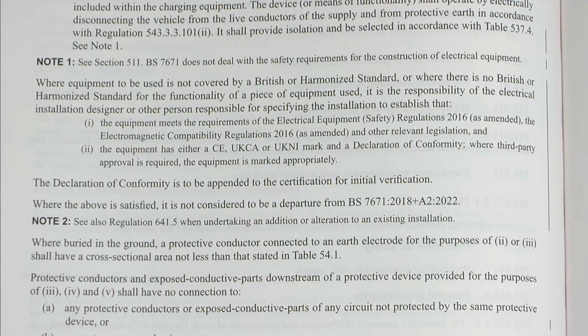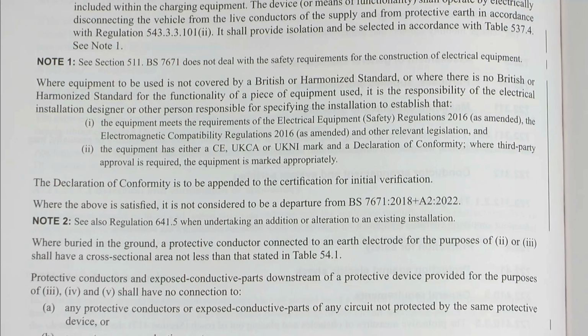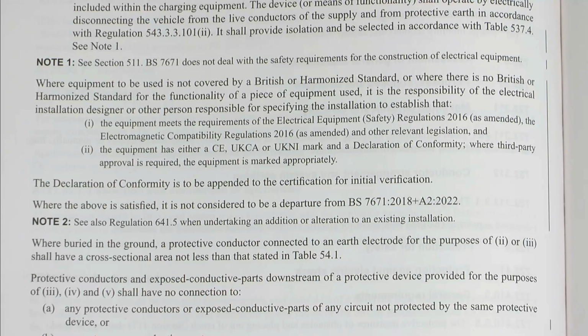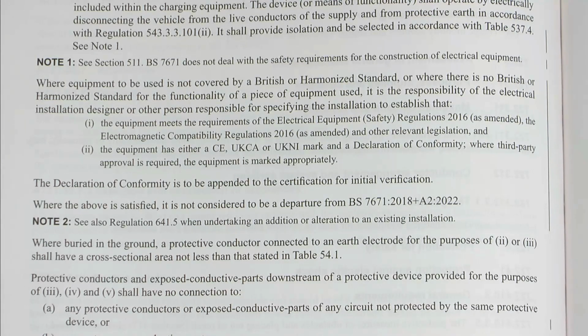So we've got where equipment to be used is not covered by a British or harmonised standard, or where there is no British or harmonised standard for the functionality of a piece of equipment used, it is the responsibility of the electrical installation designer or the person responsible for specifying the installation to establish that, number 1, the equipment meets the requirements of the Electrical Equipment Safety Regulations 2016 as amended, the Electromagnetic Compatibility Regulations 2016 as amended, and other relevant legislation, and the equipment has either a UK CA or CE or UK NI mark, and a declaration of conformity where third-party approval is required.